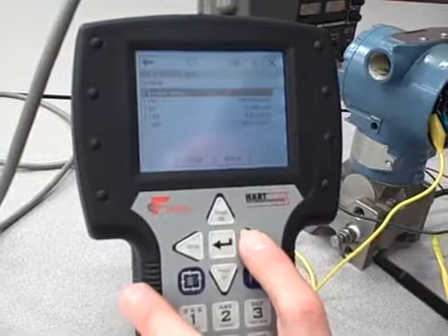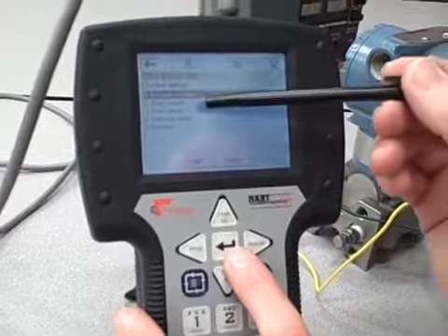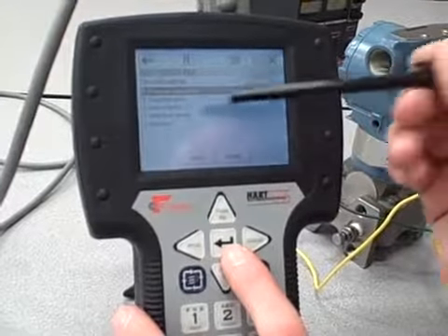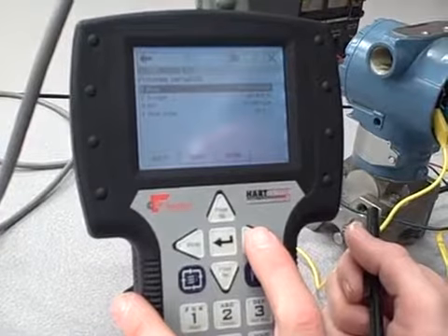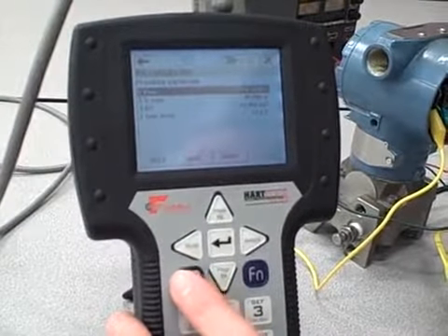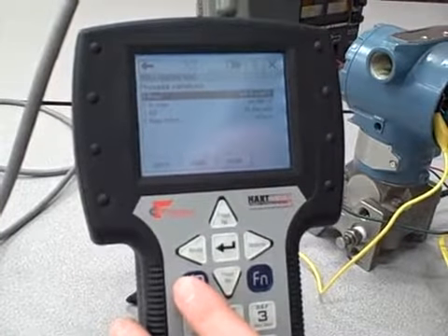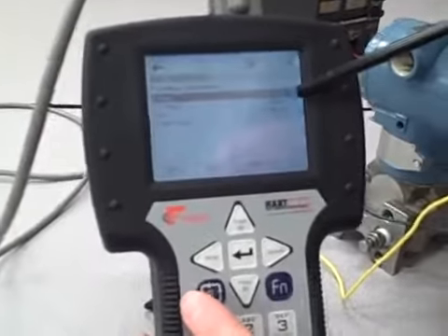So first I'm going to descend into the device setup menu. I'll push the right arrow key and I see a list of options: process variables, diagnostic service, basic setup, detailed setup, and review. Process variables, at this point I'm looking at the applied pressure to the transmitter, which, as I said before, was about 500 inches of water column. That is approximately 50% range on the transmitter for a 0 to 1,000 inch range.